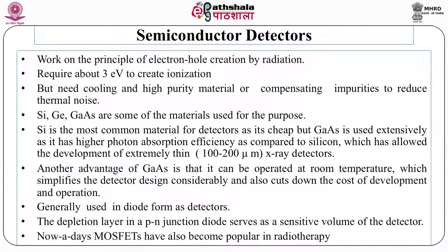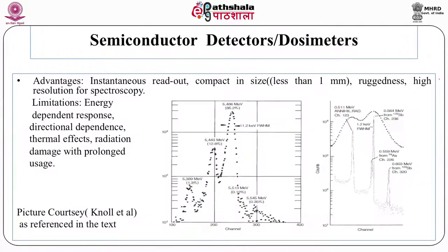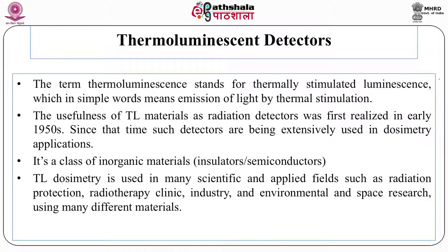Advantages of semiconductor diode dosimeters include instantaneous readout, compact size, ruggedness, and high resolution for spectroscopy — because it requires only 3 eV to produce one ion pair. Limitations include energy-dependent response, directional dependence (response varies depending on the direction from which radiation falls on the detector), temperature effects, and the fact that diodes change their response over time due to radiation damage accumulated over long periods.